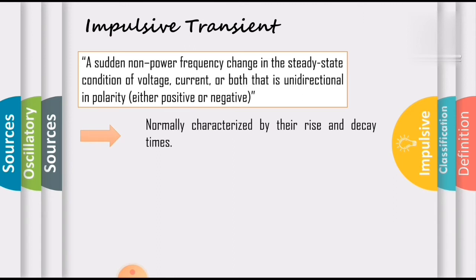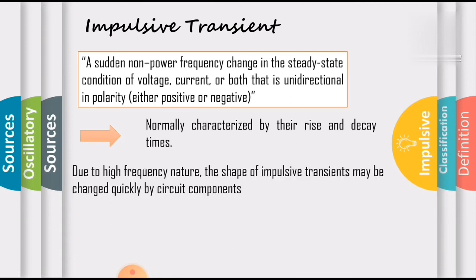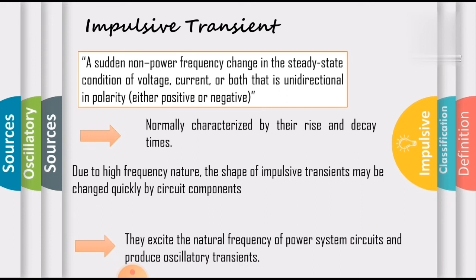Impulsive transients are normally characterized by their rise and decay times. Due to their high frequency nature, the shape of impulsive transients may change quickly by circuit components and may have significantly different characteristics when viewed from different parts of the power system. They are generally not conducted far from the source. Impulsive transients can excite the natural frequency of power system circuits and produce oscillatory transients.